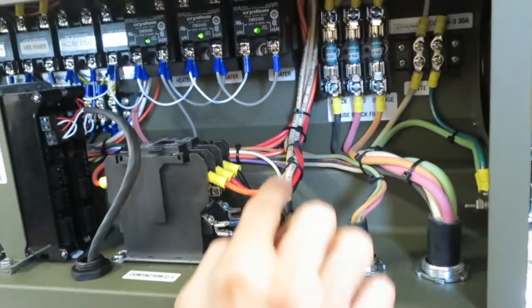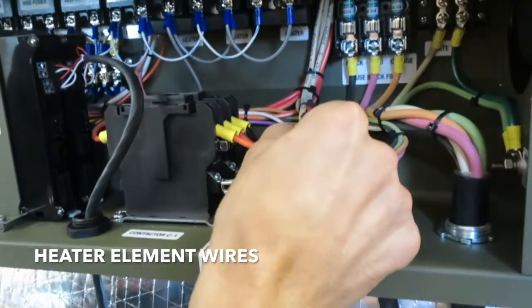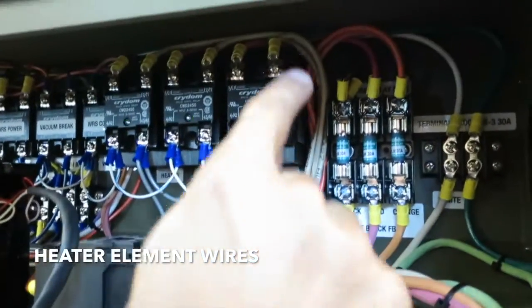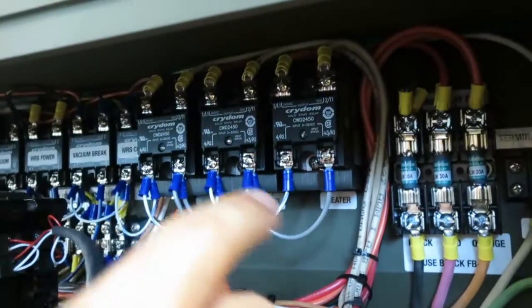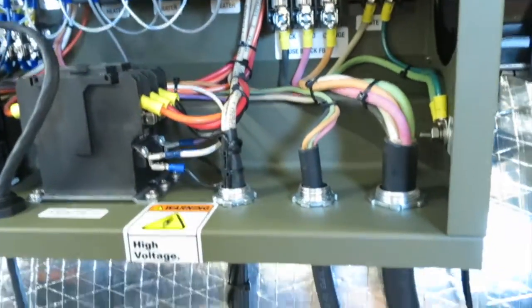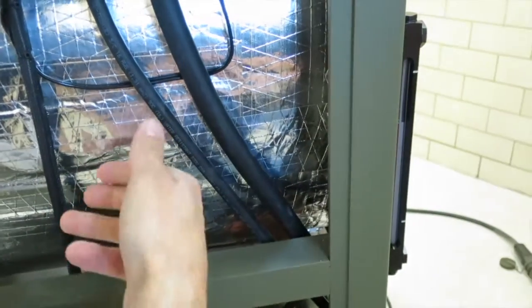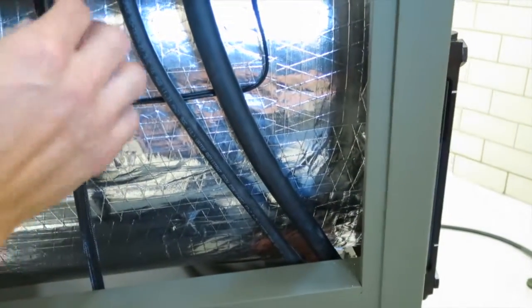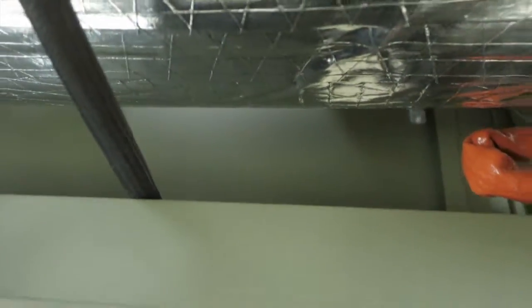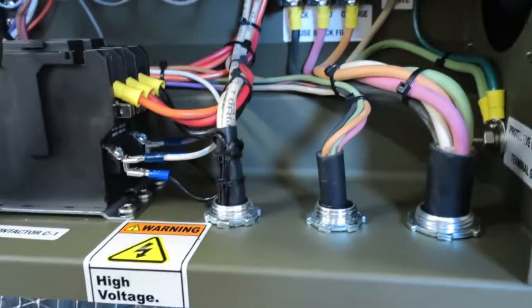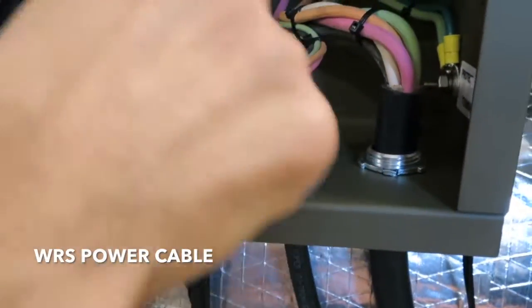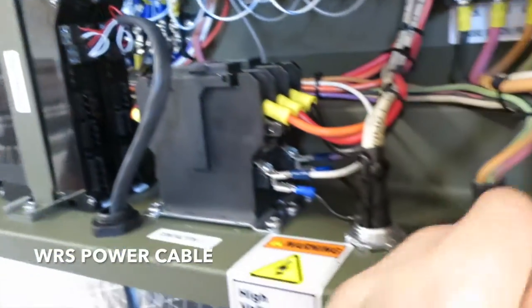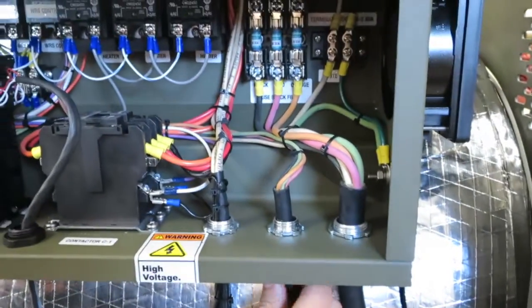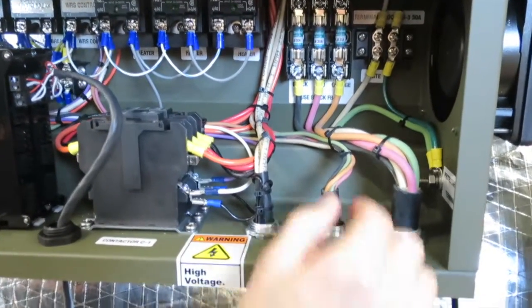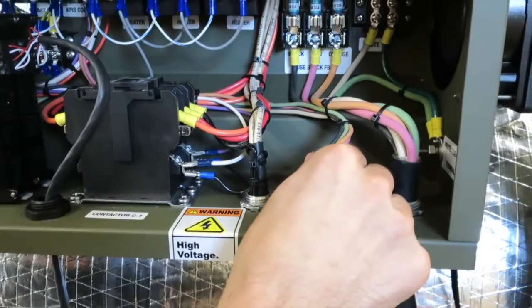Right here, I have the wires to the heater elements. It's these three white wires. If you follow them up, they go to those relays, which we'll talk about here in a second. But this goes down to the back to the heater elements, which sit in the jacket to provide the heat to heat up the water and turn it into steam. So those are the wires to the heater elements. Right here, I have a cable that goes down to the water recovery system. You can follow those over. They connect to the terminal boards. This allows the sterilizer main unit to turn on and off the water recovery system. So all power for the water recovery system is actually coming from the sterilizer main unit through that cable.